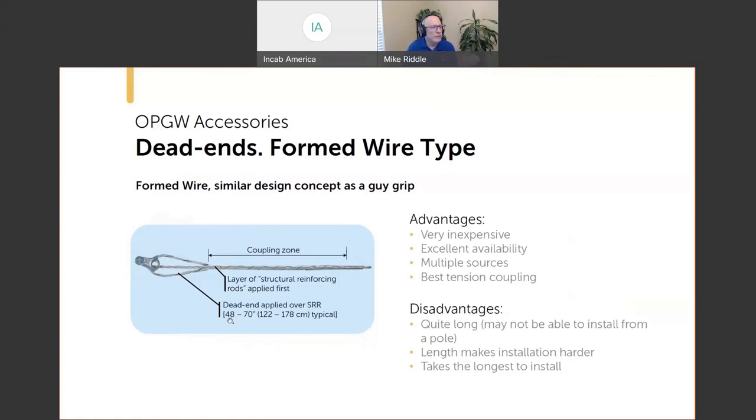So the next category of dead ends is the formed wire type. Same concept as a guy grip. For OPGW, there is first a layer of structural reinforcing rods put on the cable, and then you're applying the actual dead end, really a big guy grip, over top of that layer of structural reinforcing rods. So from a holding standpoint, that's just great. You've got a lot of protection for the cable, and you have a coupling zone that's on the order of 4 to 5 feet. Can be a little bit more sometimes, can be a little bit less, but in general, it's around that.